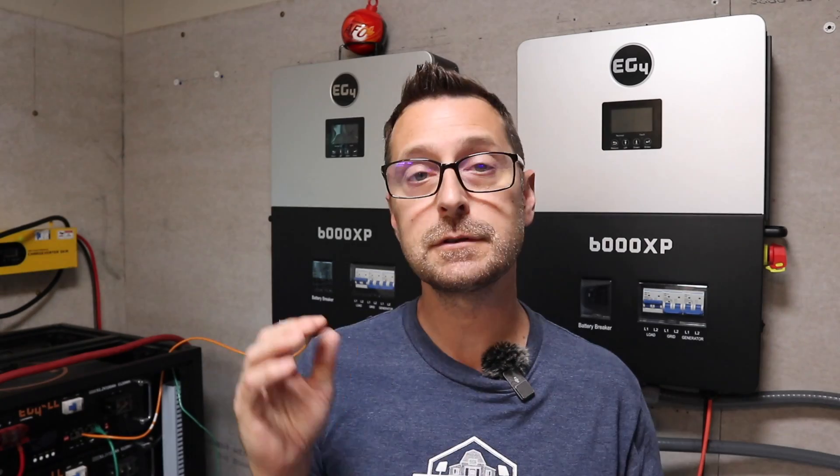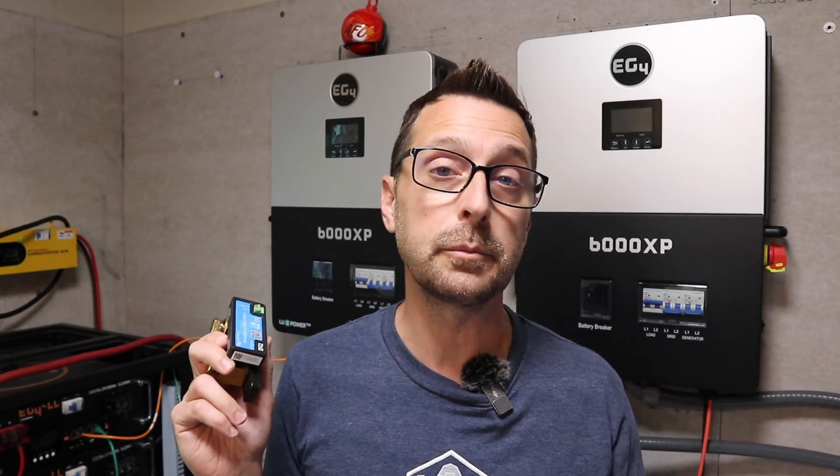At that exact moment, a few of my mini-splits kicked on — a load of maybe 1,200 watts — and it completely shut the system down, sending the batteries into protection mode. Some batteries were not reading properly and were probably well below the cutoff level set in the inverters. That's a real-world example of something that happened to me that you should be aware of. Monitoring voltage and state of charge can be a little odd at times and could cause an unexpected shutdown. I'm not an electrical engineer — I'm just hoping this real-world example can help and benefit you. Please leave a comment if you've had a similar experience.